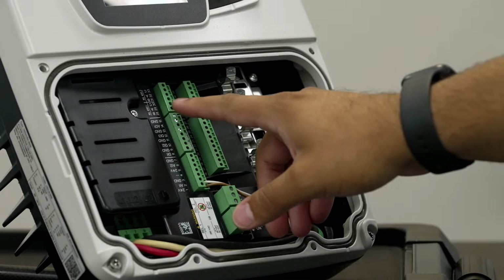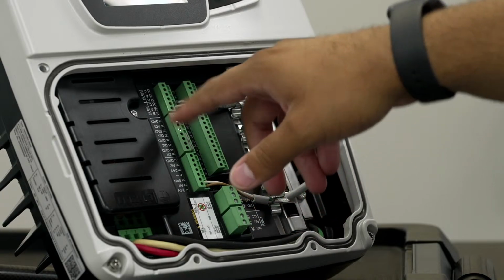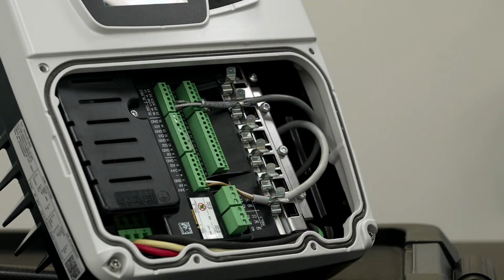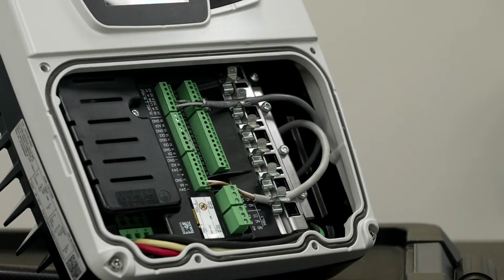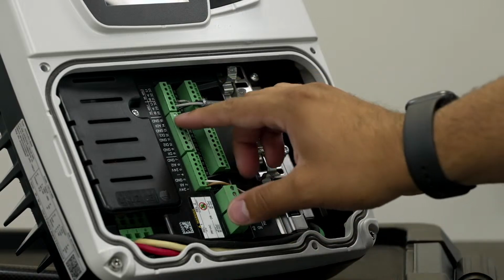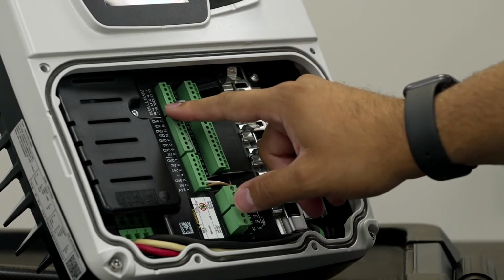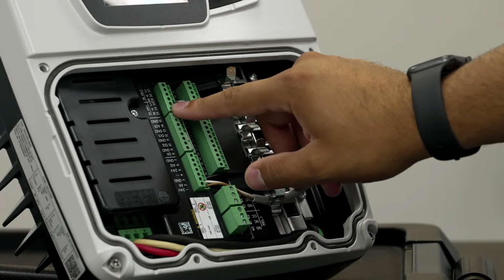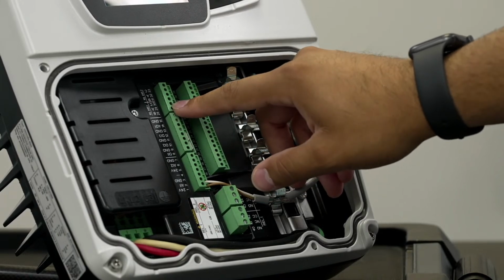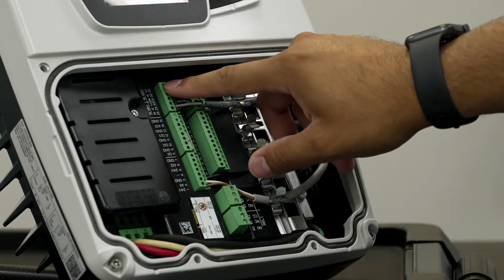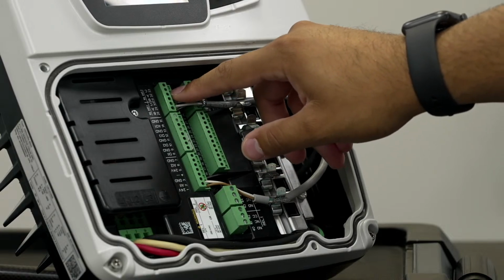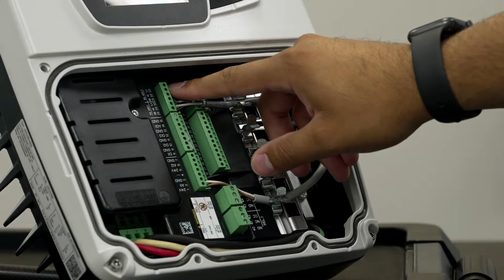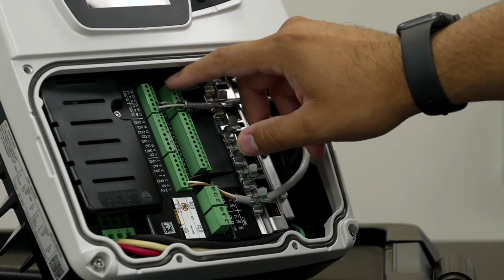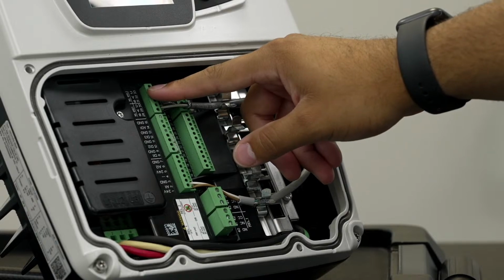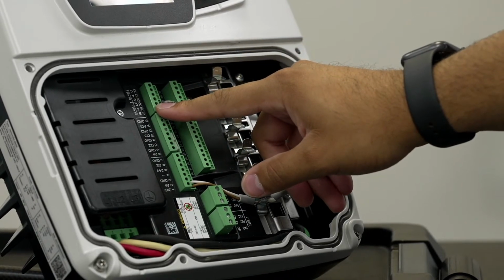But a nice thing about our communication wiring, we have a ton of different ports. A lot of VFDs on the market, you have to choose between multi-pump applications or BMS communication. With ours, that is not the case. We have 2 different banks here. One's available for multi-pump, so terminals 28, 29, 30 are for multi-pump applications. 31, 32, and 33 are available for communication to BMS or SCADA systems. So you don't have to choose. You can do both BMS communication and multi-pump capability.